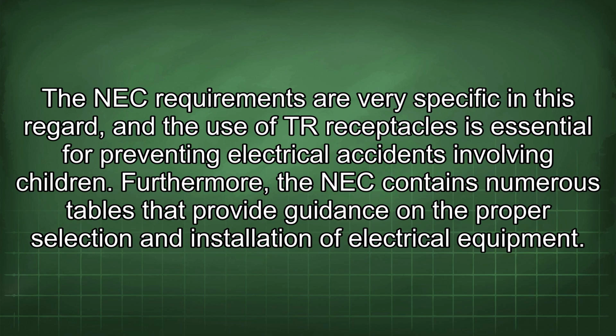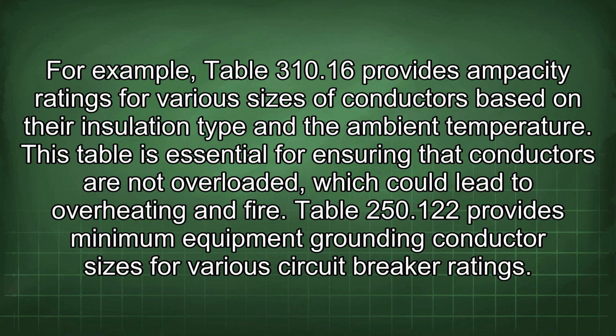accidents involving children. Furthermore, the NEC contains numerous tables that provide guidance on the proper selection and installation of electrical equipment. For example, Table 310.16 provides ampacity ratings for various sizes of conductors based on their insulation type and the ambient temperature. This table is essential for ensuring that conductors are not overloaded, which could lead to overheating and fire.